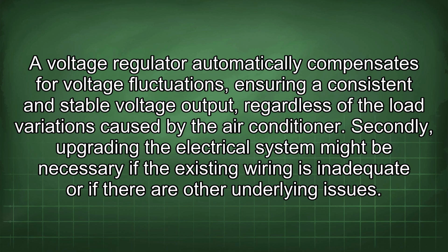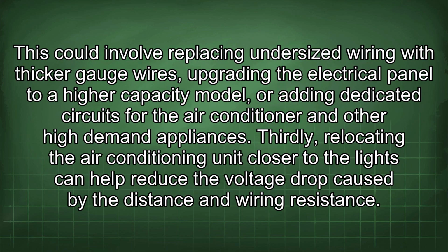Secondly, upgrading the electrical system might be necessary if the existing wiring is inadequate or if there are other underlying issues. This could involve replacing undersized wiring with thicker gauge wires, upgrading the electrical panel to a higher capacity model, or adding dedicated circuits for the air conditioner and other high-demand appliances.